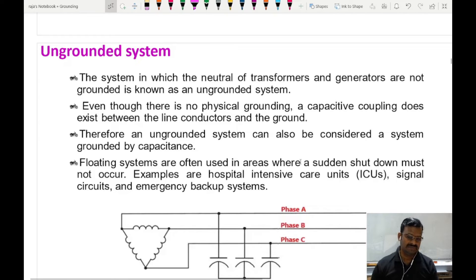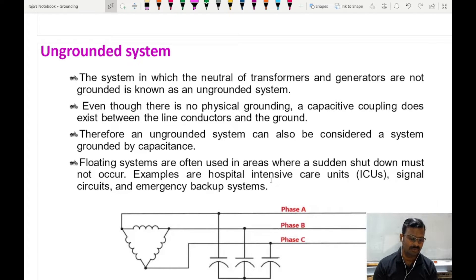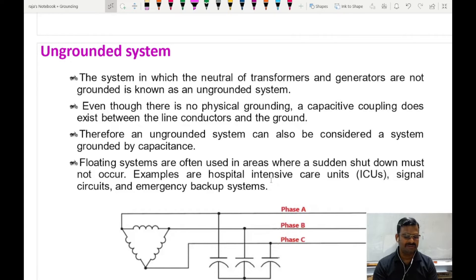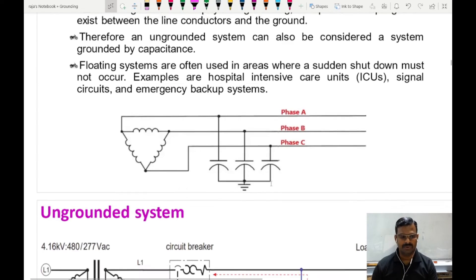Where are floating systems used? In hospitals, intensive care units, the power supply should be uninterrupted — signal circuits and emergency backup systems. In these areas, if there is a fault, the importance of the ongoing work is greater than the fault. So they give a little less preference to the fault. There is a system to find out the fault, and if it is not major, it is allowed to continue for a certain time until an alternate source of power is found and a switchover takes place. This is the main purpose of the ungrounded system.